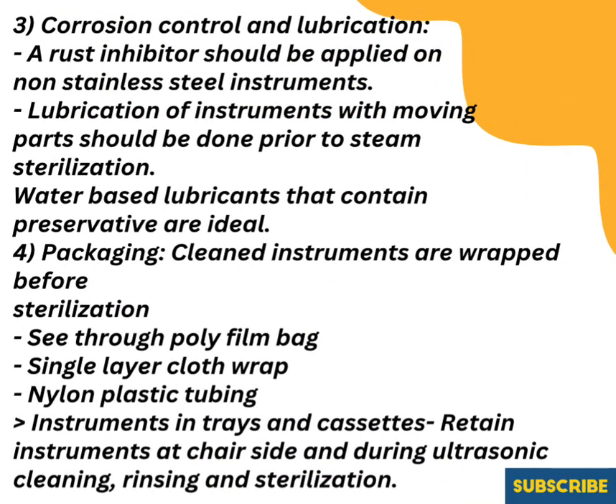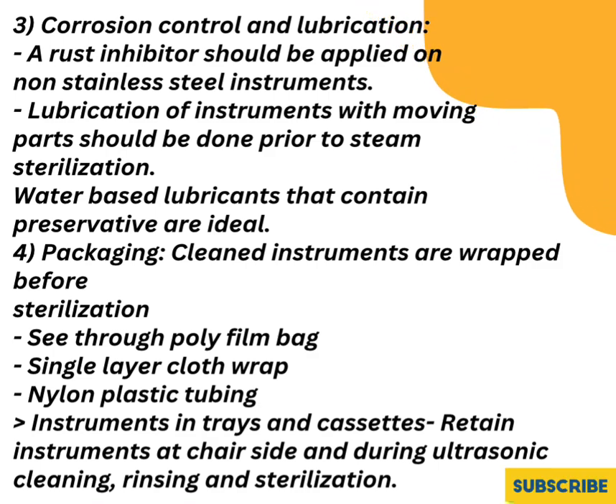3. Corrosion control and lubrication. A rust inhibitor should be applied on non-stainless steel instruments. Lubrication of instruments with moving parts should be done prior to steam sterilization. Water-based lubricants that contain preservative are ideal.